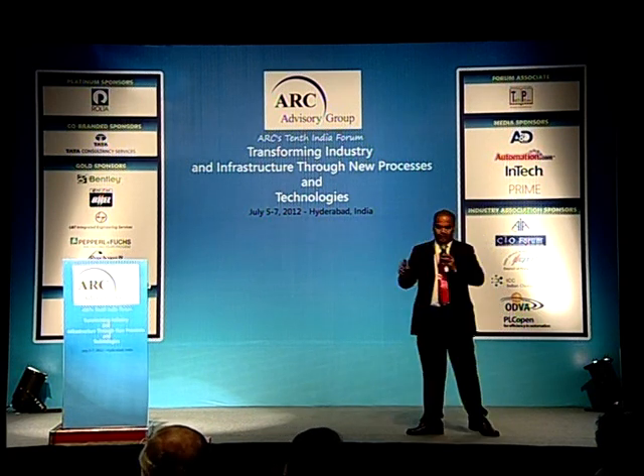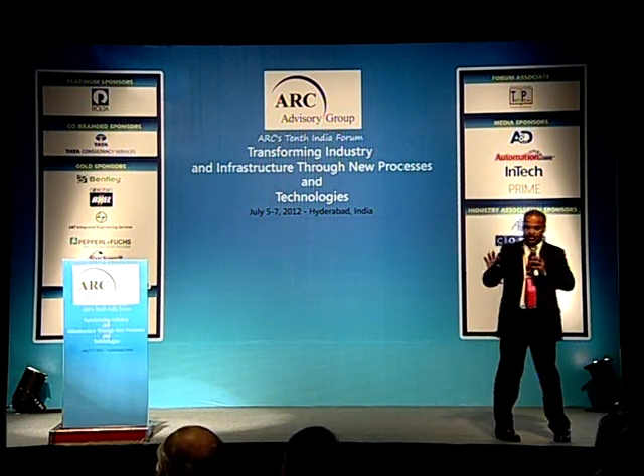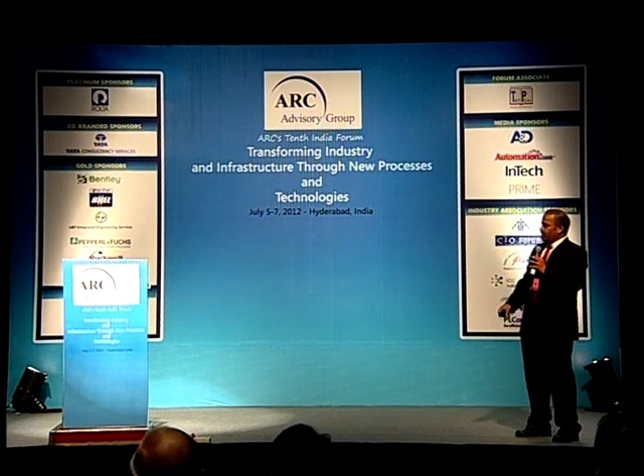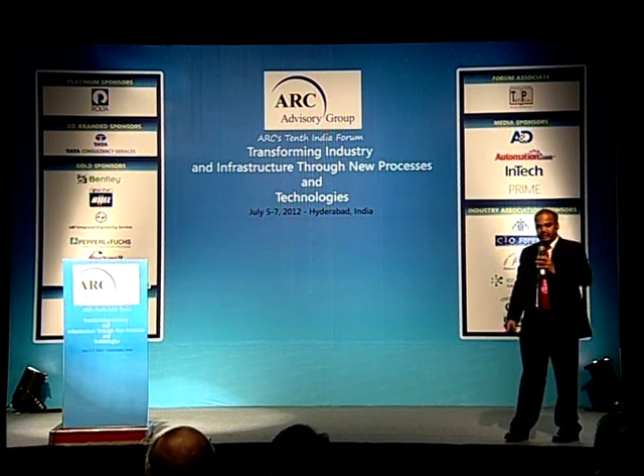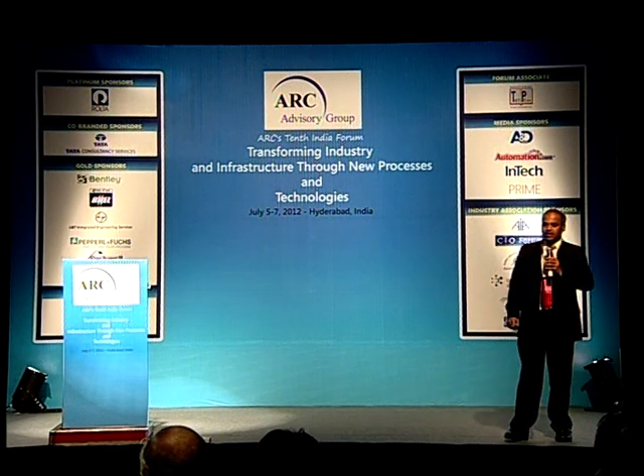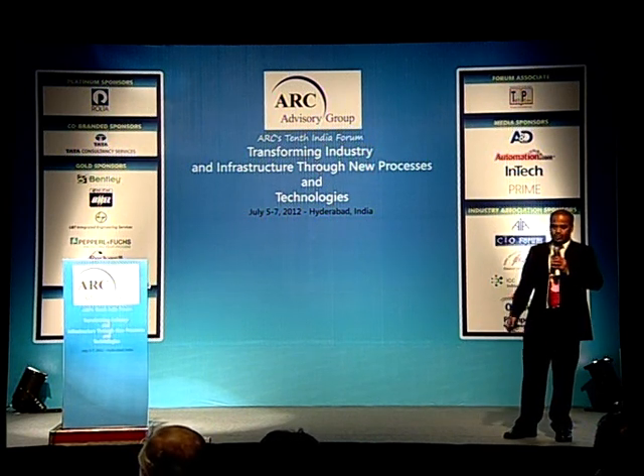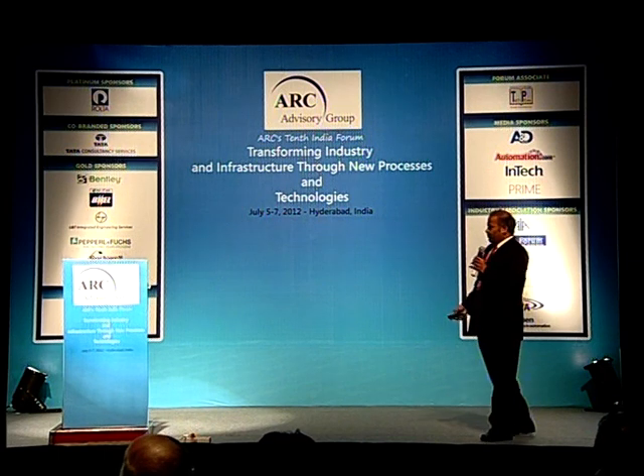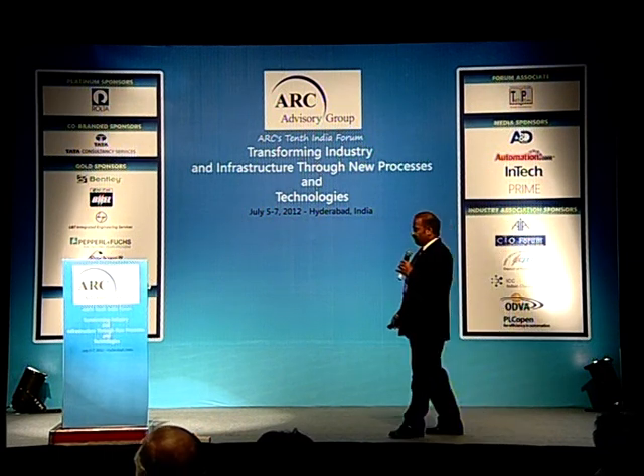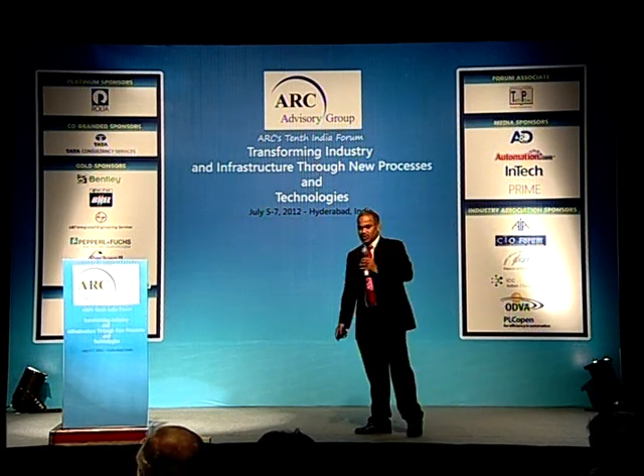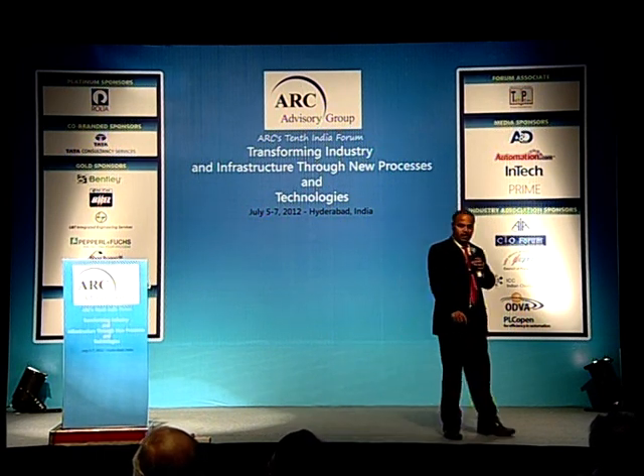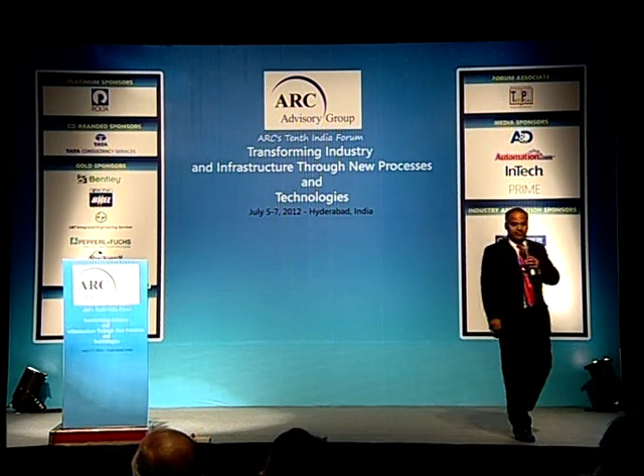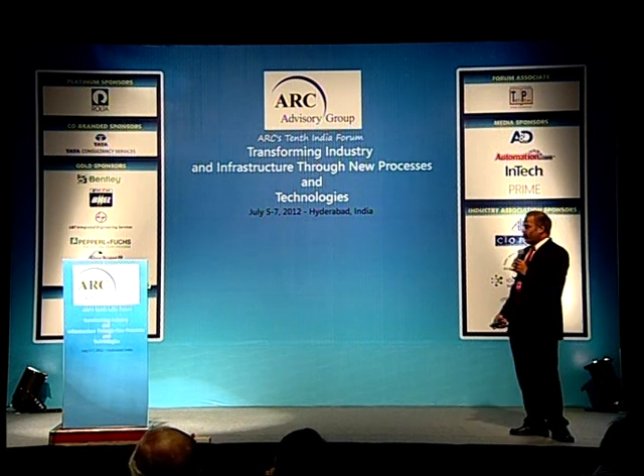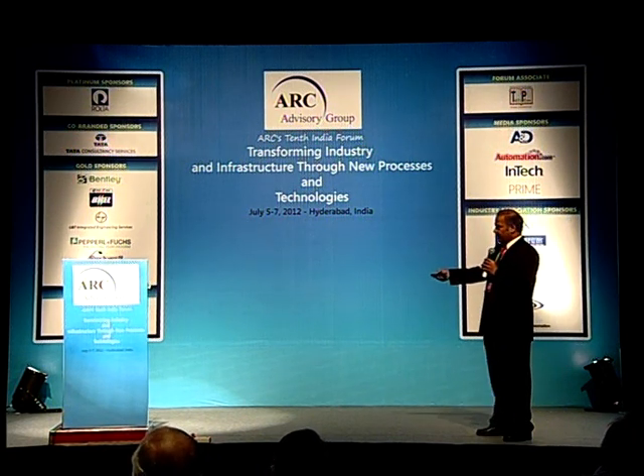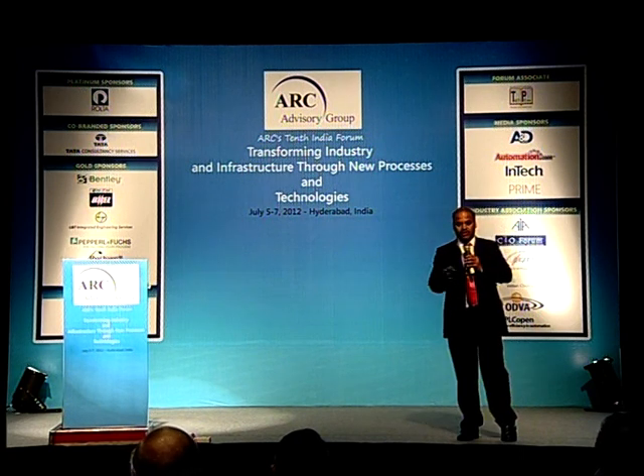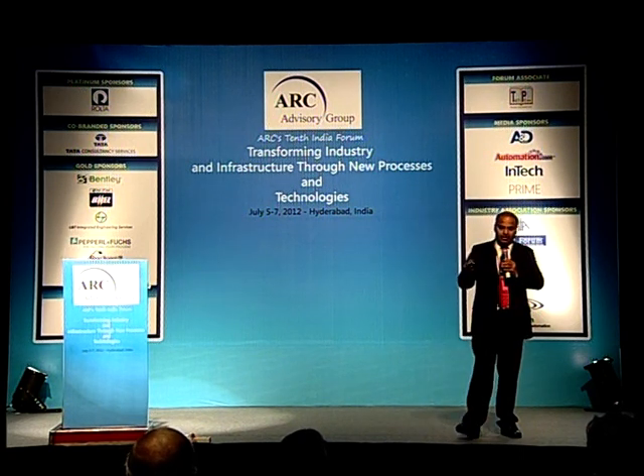Since we are in the oil and gas application location, we know how the locations are classified. Basically, we follow either the European-based or the North American-based system. We call them zones or Class 1, Division 1s. A typical example is a storage tank, and we would classify areas as Zone 0, Zone 1, and Zone 2, depending on the intensity level of the combustible substance.